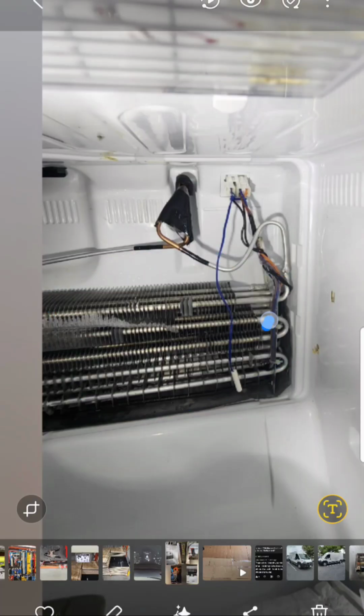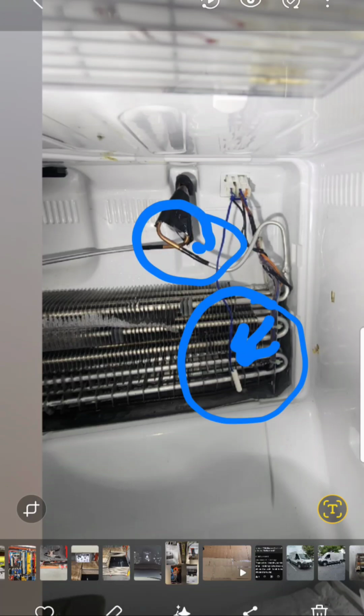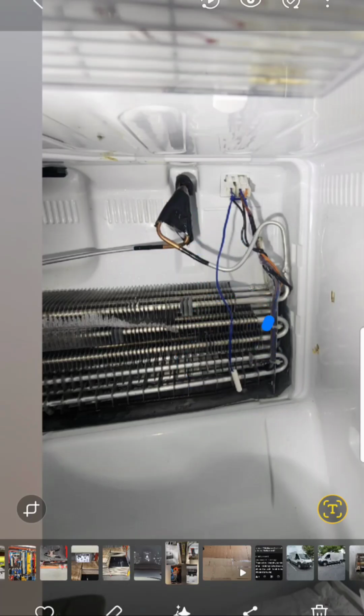But the thing I did find was that probe right here was just hanging. It was just hanging in the bottom. It should have been connected to one of these lines right over here, preferably up around the insulation right here. Instead, it was hanging down there, and that could be what caused that error code to come up, because it wasn't really sensing the defrost heat, that the defrost heater was on. So that's something else to look at.